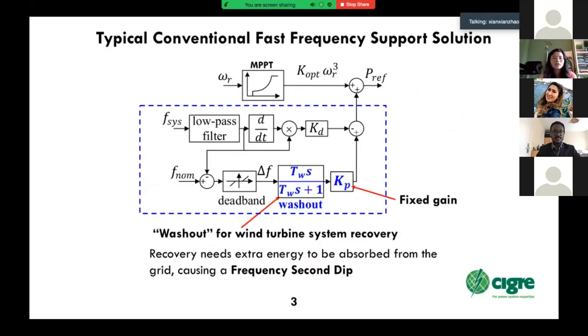In the typical conventional fast frequency support method, the washout component or similar components are used for wind turbine system recovery. Since the recovery needs extra energy to be absorbed from the grid, usually a frequency second dip appears. The fixed gain of the frequency support loop is not suitable for providing consistent good frequency support at different wind speeds and wind power penetration levels, because at different wind speeds, a wind turbine system has different stored rotational energy. And at different wind power penetration levels, the frequency support requirements are also different.